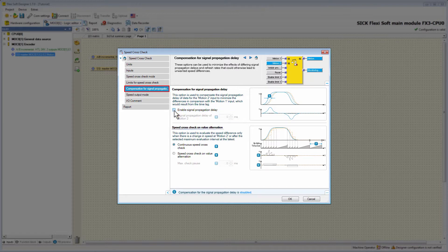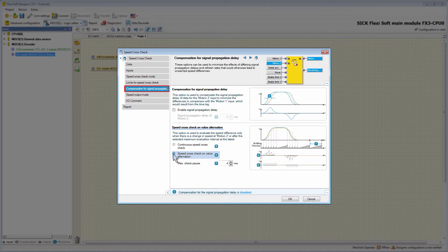Furthermore, you can choose between continuous evaluation or Speed Cross Check on Value Alternation when the speed difference is evaluated. We can select Continue Speed Cross Check for continuous evaluation, or select Speed Cross Check on Value Alternation, where the evaluation only takes place if the value of Motion 2 changes. If the second option is selected, you need to define the Max Check Pause — this sets after what time the evaluation must be carried out if there was no value alternation. This time is necessary to discover potential encoder errors, like for example a cable break.